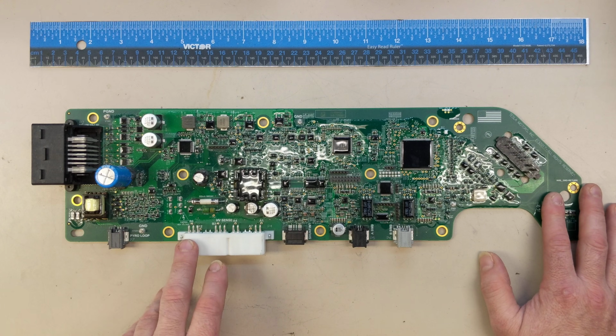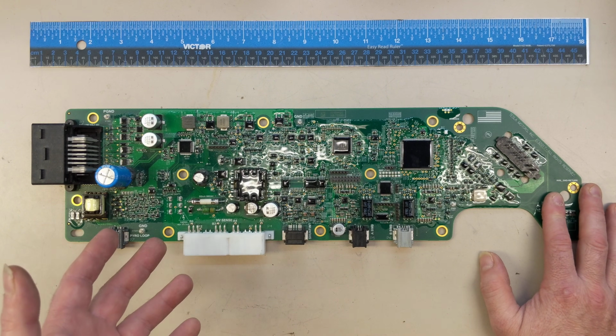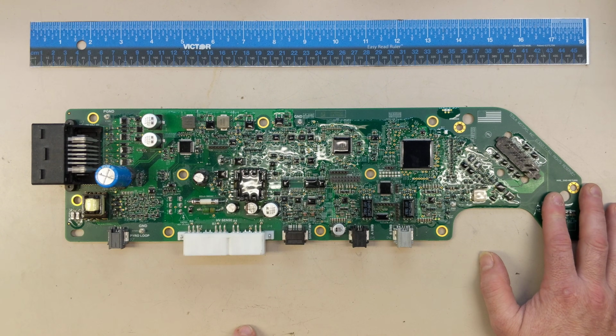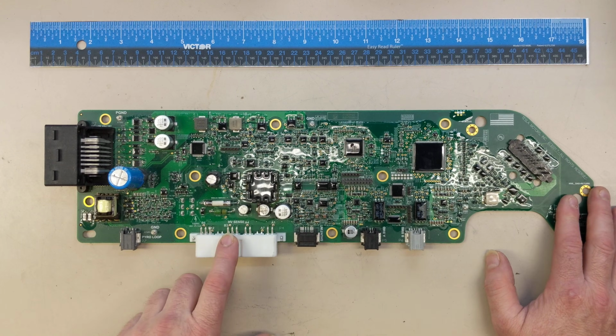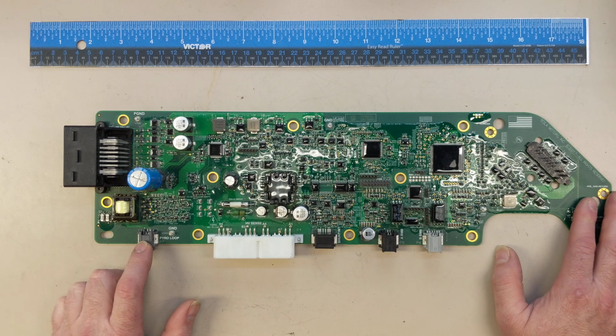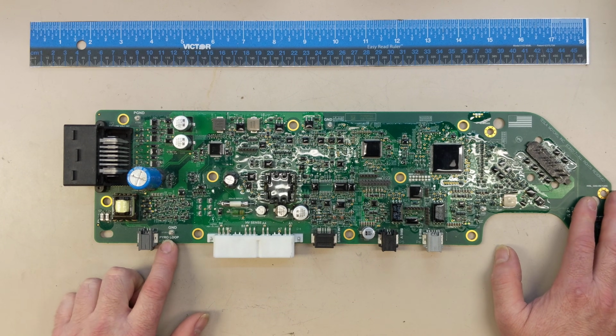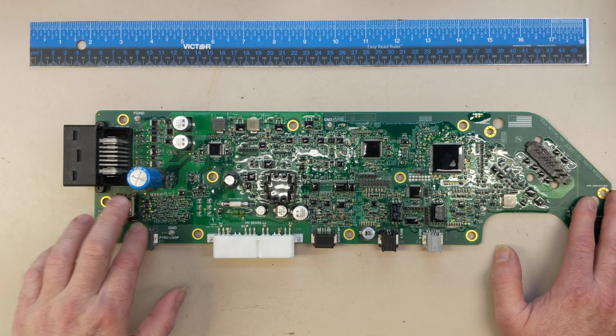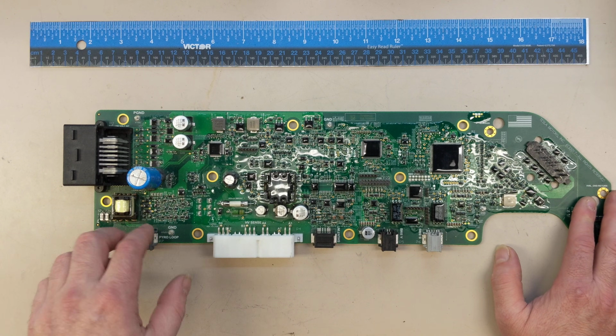It also has software trip thresholds that they can program in the software, so that if they see the current profile behaving like a short circuit, they can trigger the pyro. The pyro is triggered from this circuit. It says pyro loop here. There's a galvanic isolator and then some transistors to drive it.